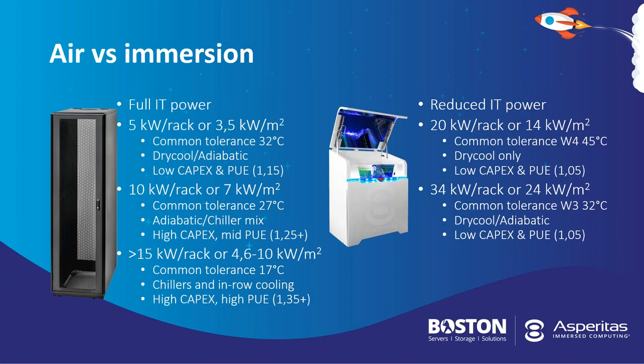You are going to be requiring a mix of adiabatic cooling and chillers, which means your overall energy consumption is actually going up, because your overhead is going to go up, you need to facilitate chillers, but also your capex is going up. Chillers are expensive, and therefore your PUE also goes up, to approximately 1.25.